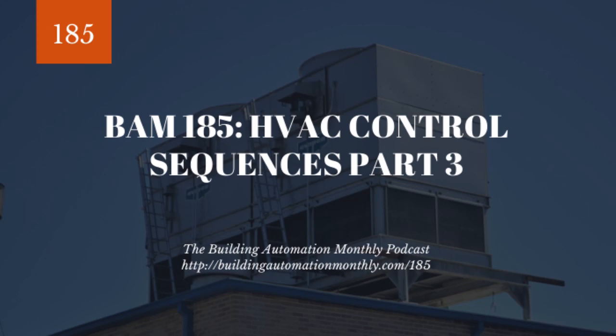So cooling mode, pretty straightforward, right? We are going to have cooling being enabled by an enable set point, and it's going to say, hey, once our discharge air temp set point is X and we've gone above it by Y, that indicates a need for cooling. Cooling mode's enabled, and then the cooling mode sequence is going to start to operate. We're either going to turn on compressors or cooling coils and open those up and control to our supply or discharge air temp, whatever it's called. Now, if it is compressors instead of coils, I mean, coils are straightforward, right? You use a PID loop, you set your integral and your proportional gain so that it properly controls, and then you control the output to the cooling valve.